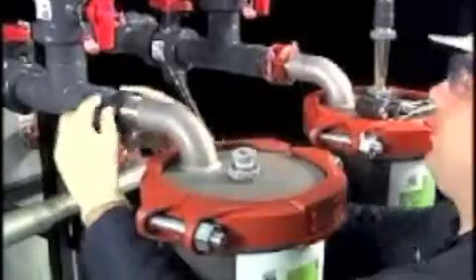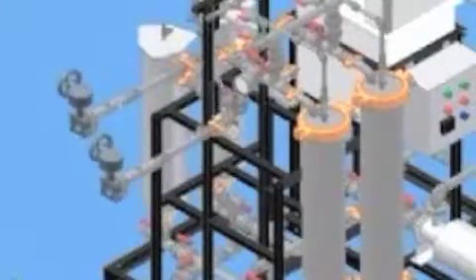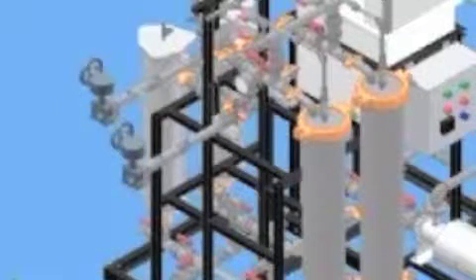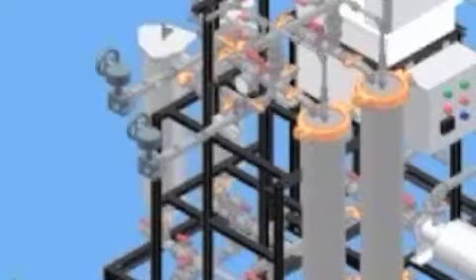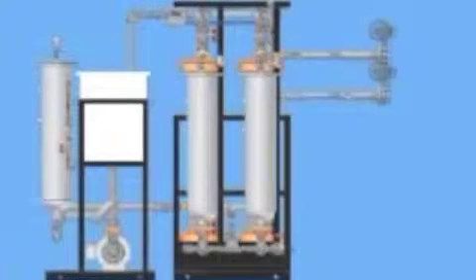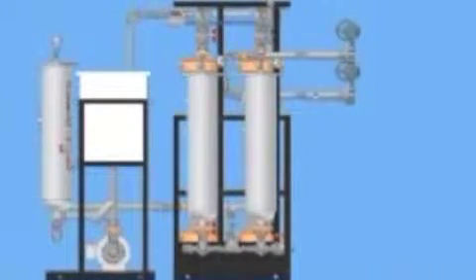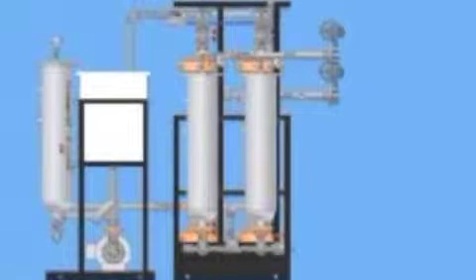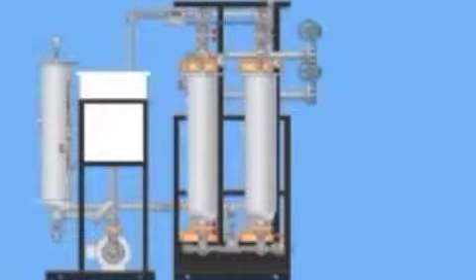Lubricate the outside gasket with glycerin to avoid pinching. If some of the inlet and outlet piping to the UF modules and PF vessels are not level, or the PF or UF housing are not vertical or true, adjustment is needed to be level. The goal is to have the inlet piping to the UF module, outlet piping from the UF manifold, and the ED paint manifold level and square to each other. If not done properly, it is likely that a leak will occur.